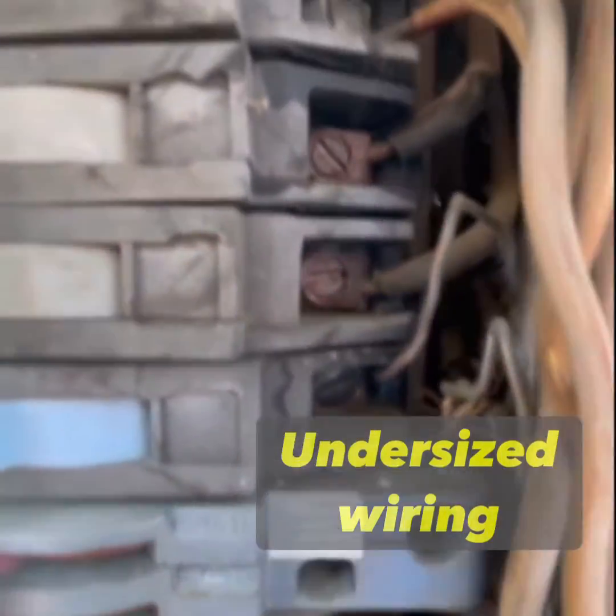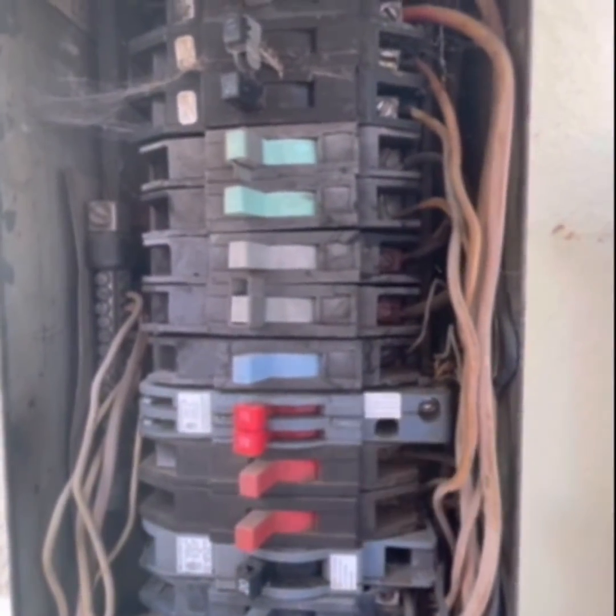A few other issues not related to this panel's design per se: a lot of undersized wiring, some moisture intrusion, breakers from different eras of this brand — it's just a mess of wiring in here. There's also some overheated wiring, and you can see there's a missing breaker tie up here. Those are just a handful of things we can see going on right here.